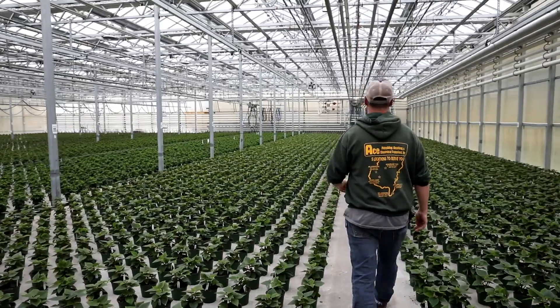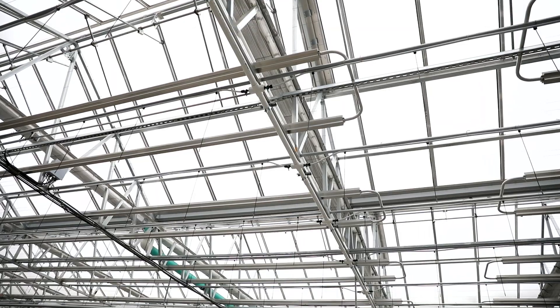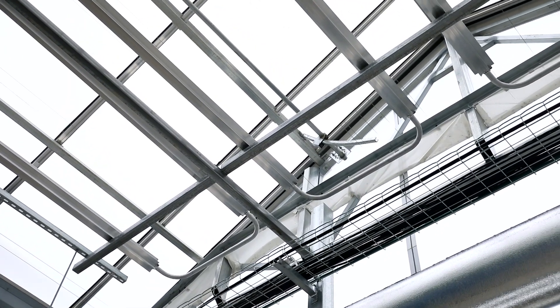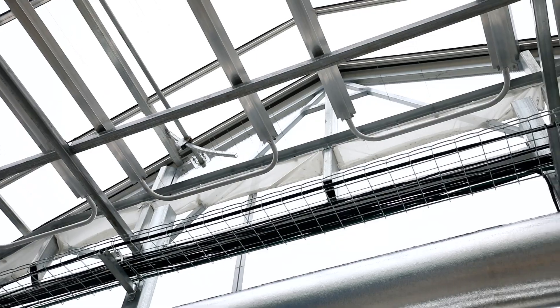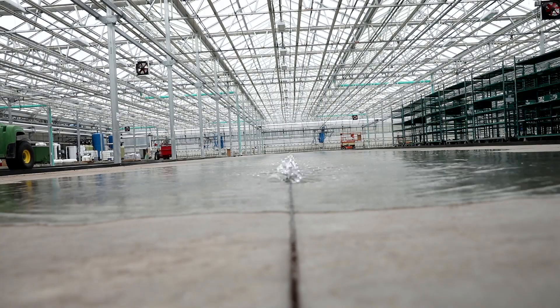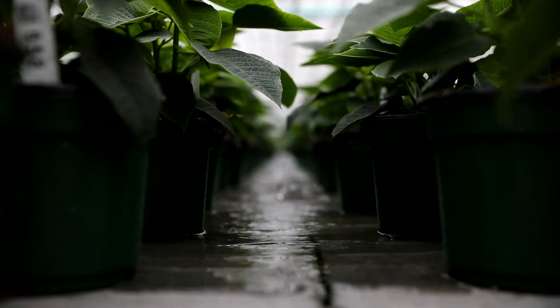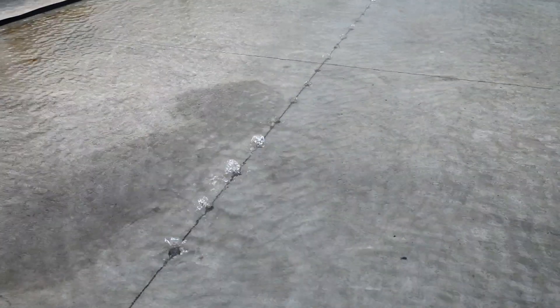About 25 acres of concrete heated water collection floors are Biotherm heat. We have hot water in the floor using either half-inch or three-quarter-inch tube. We also have starfin in the ceiling to give us heat for our air, snow load, and all those different things we have to deal with. The other half of our Biotherm relationship is flood floors. We built about 110,000 square feet the first year and we've built flood floors for all of our high-end space ever since. The one we're standing in right now was built this past winter — about 180,000 square feet — again, Biotherm heat and Biotherm flood floors.